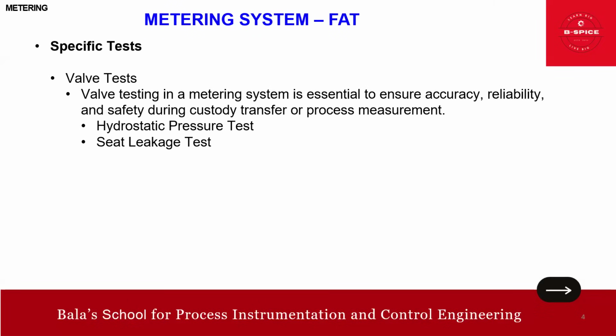Pressurize one side of the valve, right? And monitor the leakage past the seat, okay? So what is the standard to be adopted? API 598 or ISO 5208. This is about the leakage.